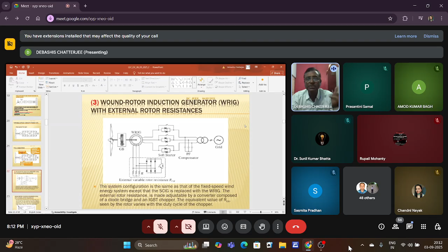Now these two are okay. Now came the slip ring type of generator. Slip ring, right? Slip ring type of generator. Now slip ring generators have some advantages. What is the advantage? The main advantage is that the rotor is accessible. Now when the rotor is accessible, you can do something like insert some resistance in the rotor. If rotor resistance is inserted, what will happen? Now you can shift the characteristics, right?